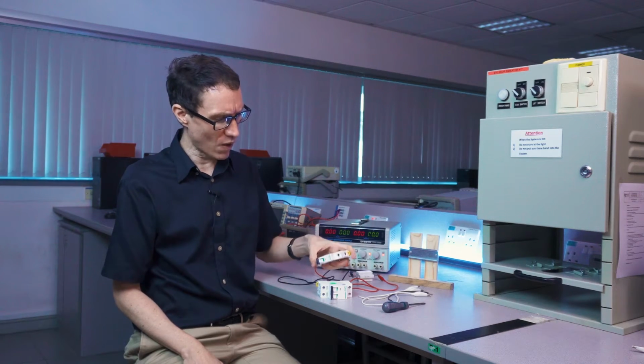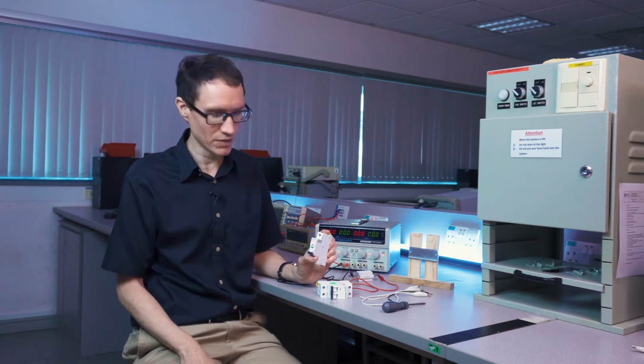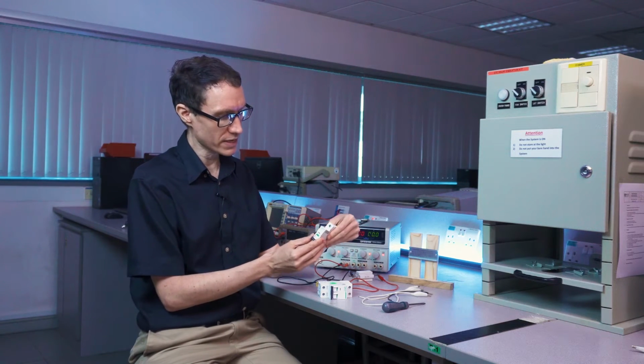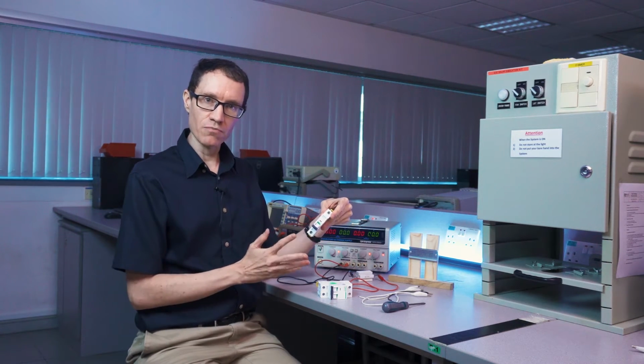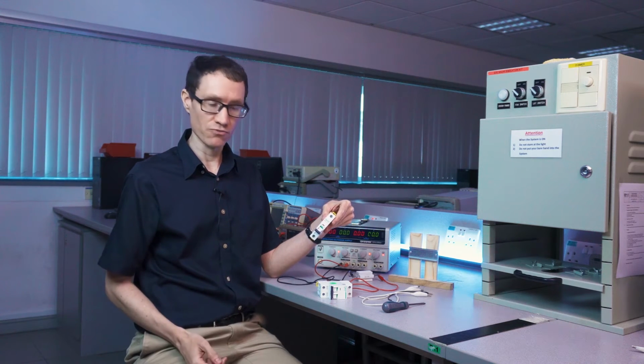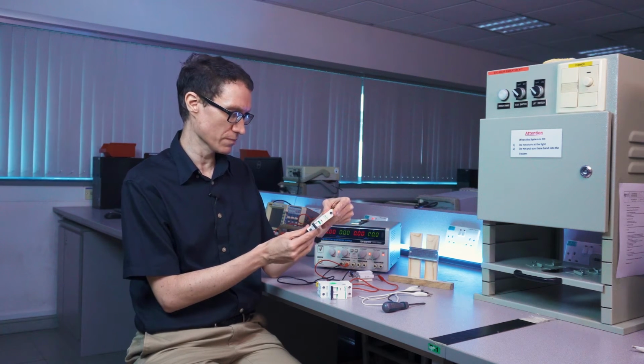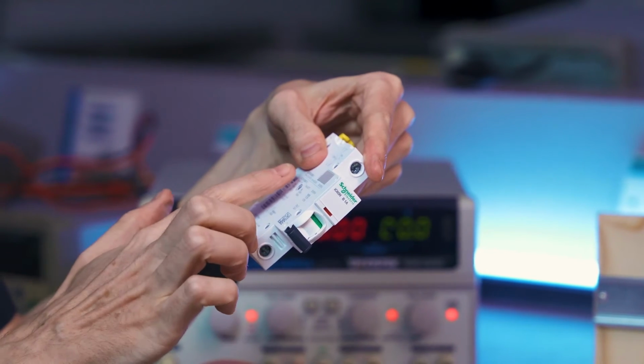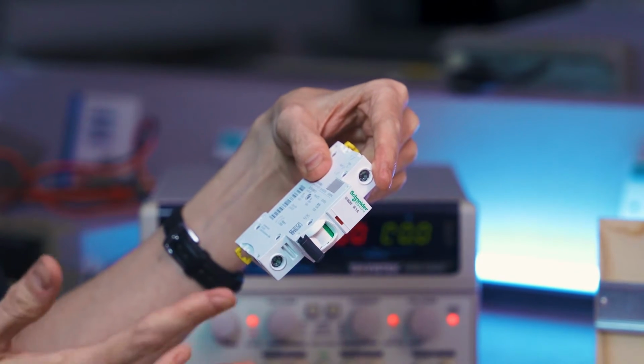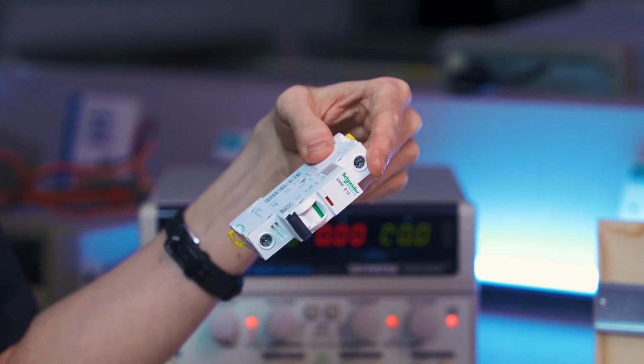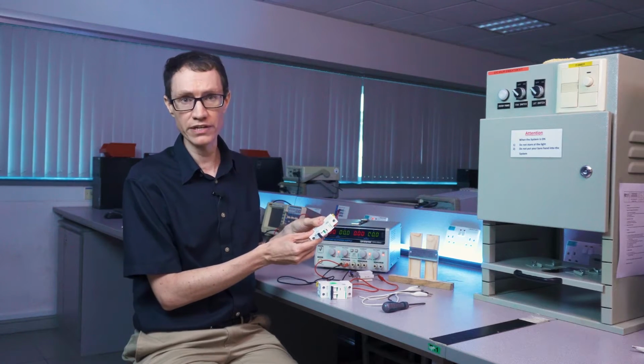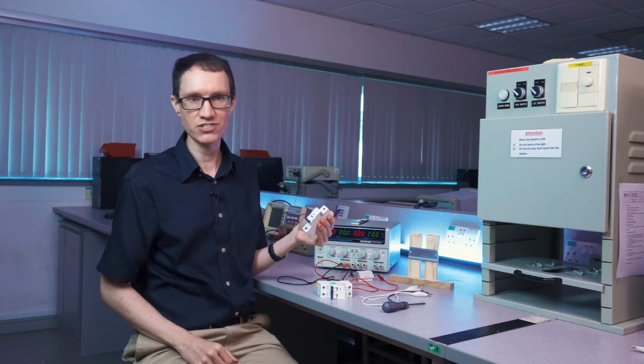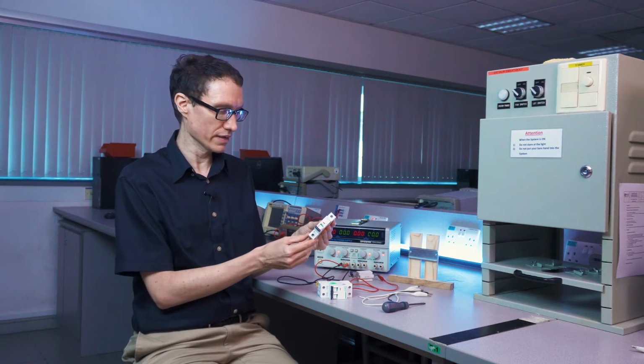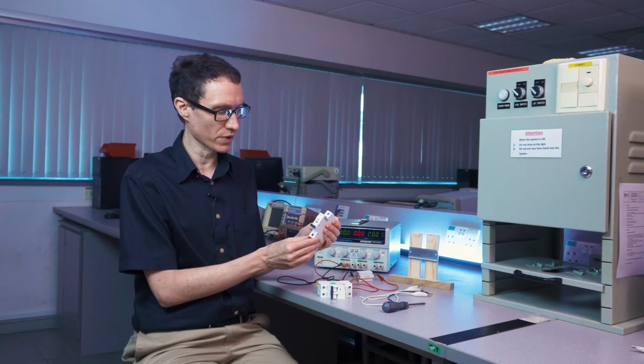These circuit breakers here are white color. I find that that's very common in Europe and in Asia. In North America, circuit breakers tend to be colored black. I don't know the reason for that, but that's the way it is. Circuit breakers care more about current than they do about voltage, but they do have a rated voltage. These circuit breakers right here are rated for 230 volts or 400 volts. 400 is referring, I suppose, to three-phase, and the 230 is referring to a single phase, but it's just a 1-pole breaker. And again, the current is what really matters here going through the breaker.